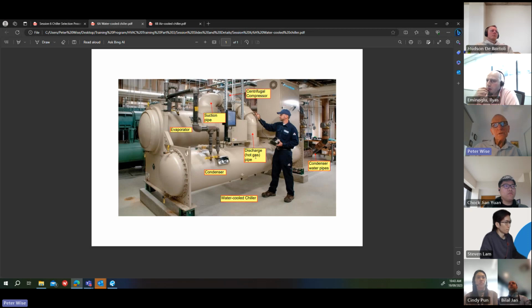So here's that water-cooled chiller we looked at before. This is the condenser heat exchanger. This box on the end here, that's called the water box. The evaporator up here has a water box as well, but normally you don't need to clean the evaporators every 12 months because that's a closed system for the evaporator. The condenser is in an open system, normally, if it's connected to a cooling tower. So every 12 months, they have to take the end off, or the water box, off the condenser. So undo all these nuts and drop it on the floor. It's very heavy. It's made of steel normally, or stainless steel. And they have to clean out the tubes in the condenser. So that's quite a job to do that and to get that off.